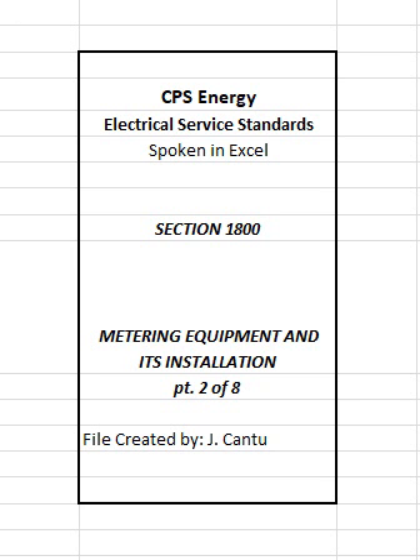Type of transsocket: maximum demand load. Code 23, overhead, 400 amperes, 144 kVA, 208V, 333 kVA, 480V. Code 24, overhead, 800 amperes, 288 kVA, 208V, 665 kVA, 480V. Code 25, underground, 400 amperes, 144 kVA, 208V, 333 kVA, 480V. Code 26, underground, 800 amperes, 288 kVA, 208V, 665 kVA, 480V. It is critical that the correct transsocket be installed for each service installation due to the pre-wired configuration of internal equipment. Where service is underground, the line conductors must enter the bottom of the transsocket and connect to the bottom terminals.